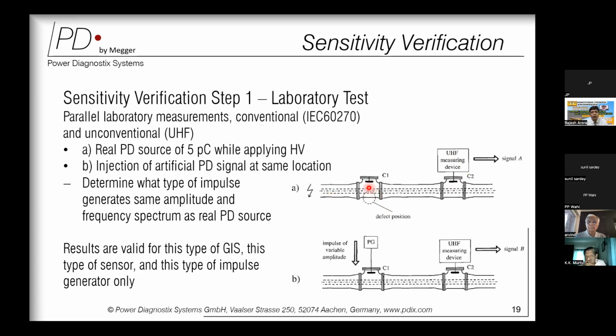We will raise the voltage and adjust the defect in such a way that the electrical measurement as per the conventional IEC 60270 method measures 5 picocoulombs, because that is the acceptance criterion. Once the equipment measures 5 picocoulombs, we note down the UHF pattern and the voltage recorded by this UHF sensor. We remove this artificial defect, and at the same point we use an artificial pulse generator and inject a variable pulse into the same UHF sensor. We keep increasing the voltage of the pulse generator till this UHF measuring device records the same voltage level and the same pattern.